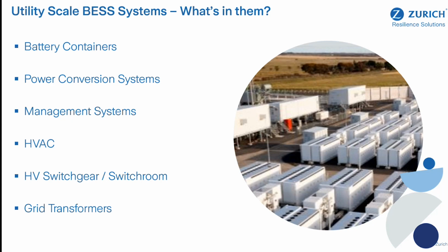In addition to that, you need management systems. Connecting to the grid isn't a simple task. If you connect to the grid incorrectly and you're out of phase with the grid, things will explode, unfortunately, and the management systems will, for starters, on the grid monitoring side, make sure that everything is aligned. The monitoring systems also measure the internal temperatures of the batteries and operate the HVAC systems as well, because batteries tend to get warm when they've been worked.